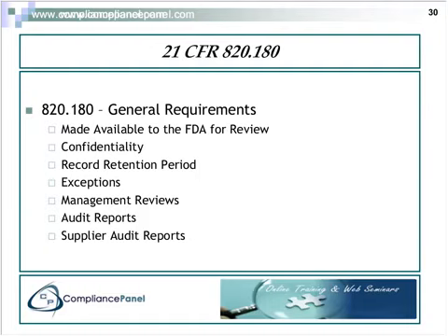There are also exceptions to what the FDA can look at when they come through. For instance, they can't look at your audit reports, your management reviews, or your supplier audits. This was done for a reason, so that they didn't have a backdoor entry. For instance, if you're buying from a supplier that is itself a medical device manufacturer, and the FDA looked at your supplier audit of that facility, they would have information relating to that site before they go do an audit there. This is much different from an ISO auditor, who has privy to look at all of these requirements.